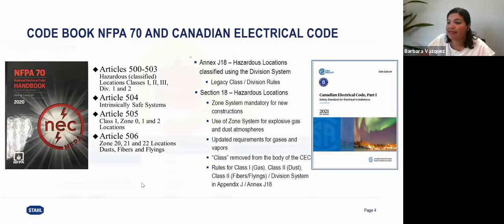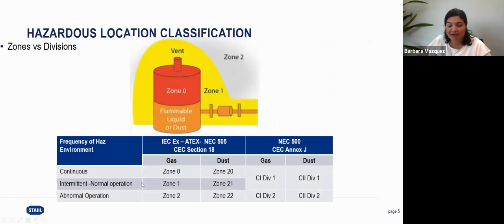Okay, so both will classify the hazardous area. A hazardous area is an area that has an explosive atmosphere, right? In this example, we have a tank full of a flammable liquid. When we're talking about zones, my zone 0 is inside the tank. We have the flammable liquid, and then we have the gases with the oxygen. So that will be zone 0. You always have the presence of the explosive atmosphere.